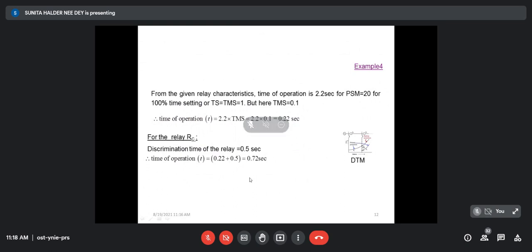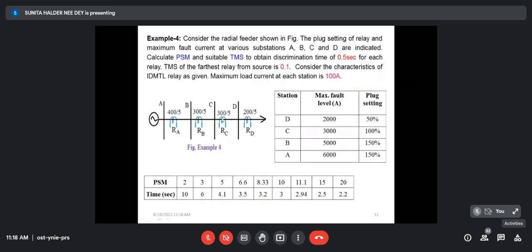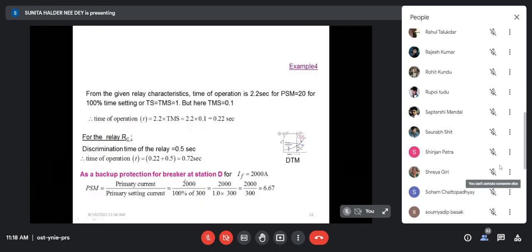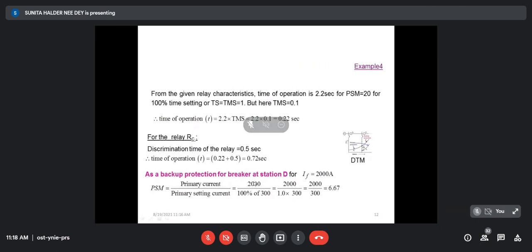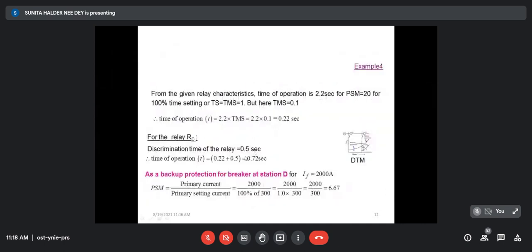RC will operate as backup relay for a 2000 ampere fault current, because fault current at station D is 2000 ampere. Plug setting at relay C is 100%. From that, we can calculate the PSM: primary current is 2000 ampere, giving PSM = 6.67. For PSM 6.67, from the characteristics, the operating time is approximately 3.5 seconds. But we have set the required time as 0.72 second.